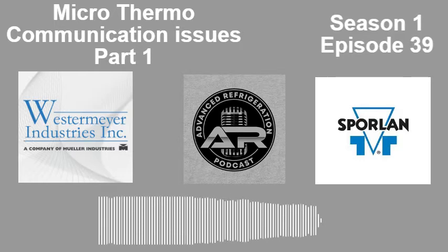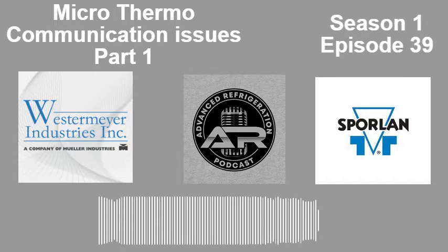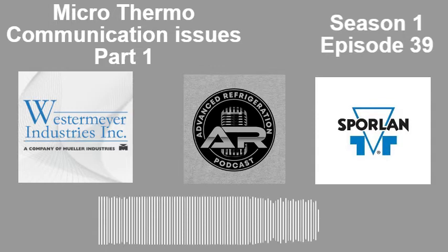So the communication that we use is FTT10. And that's 78 kilobits, 78,000 bits per second. And the topology we prefer is either star or free. And each network channel can go up to 1,640 feet. And we don't want daisy chains. I know that's a term that other communication people use because it's rightfully applied for their technology. If you do go into a startup and you see that the electrician contractor has done a Microthermo store and the network has been done in one gigantic daisy chain with a terminator on the end, run away because it's not going to work for you.